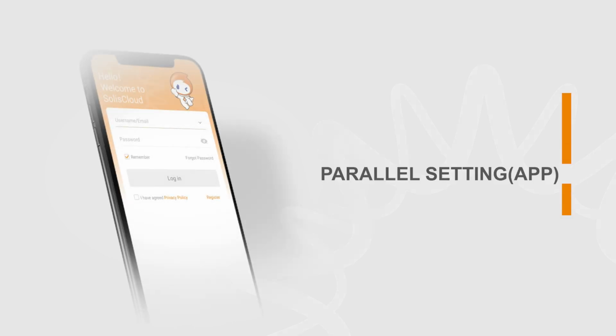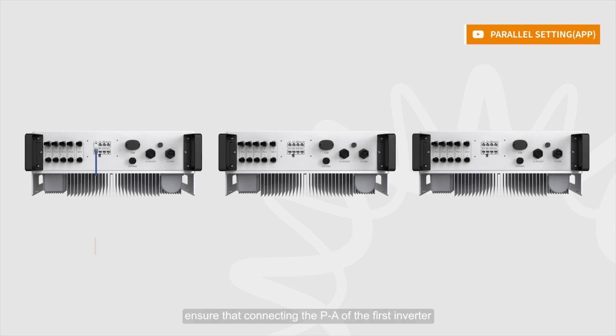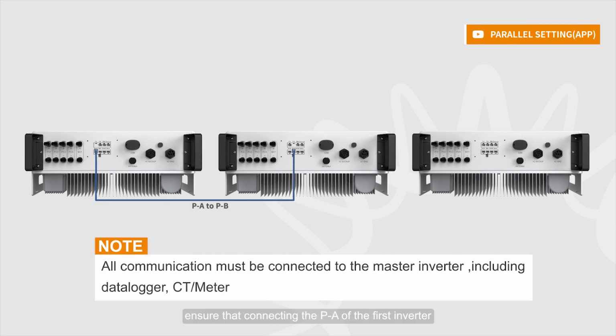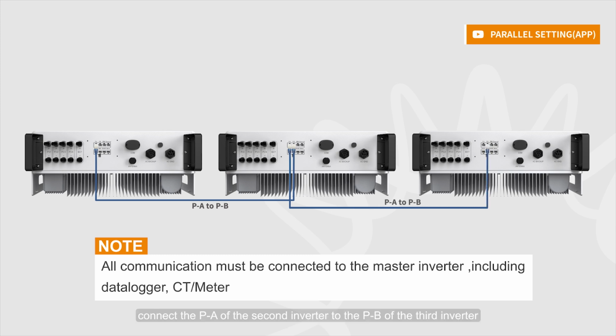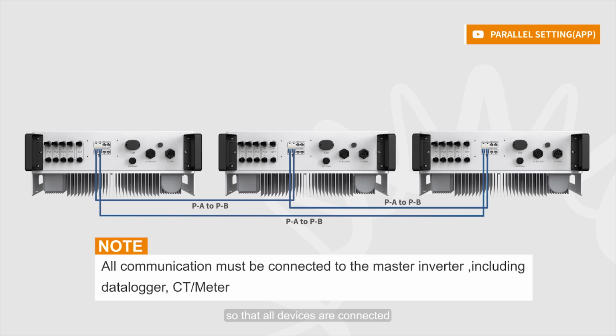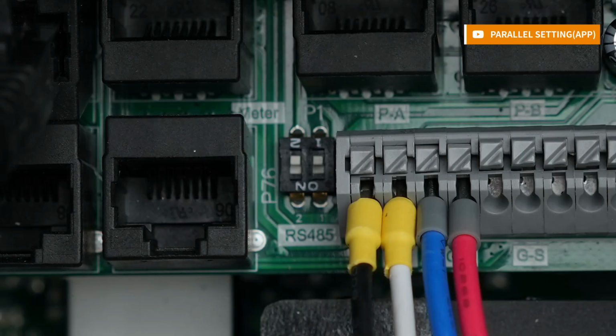Parallel setting. Before parallel setting, ensure that you connect the PA of the first inverter to the PB of the second inverter using communication cable, connect the PA of the second inverter to the PB of the third inverter, and so on, so that all devices are connected. Turn the dip switch of one of the inverters up.